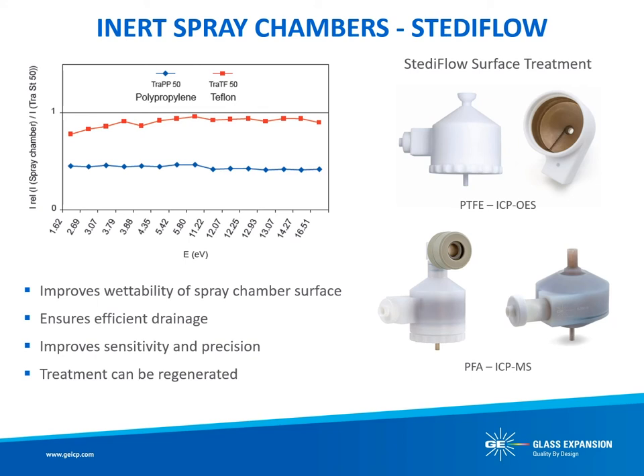Sandblasting of the plastic is a common surface treatment technique used to improve performance; however, that improvement still only provides about 50% of the sensitivity achievable with a glass or quartz cyclonic spray chamber. In comparison, the sensitivity of a StediFlow-treated PTFE or PFA spray chamber is nearly equivalent to a glass spray chamber.